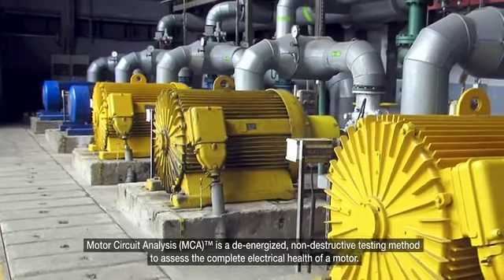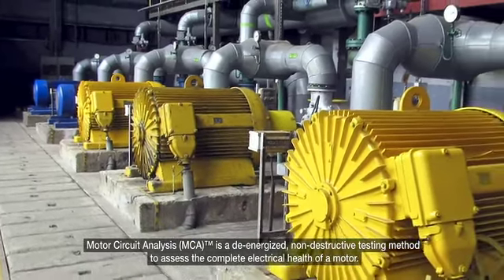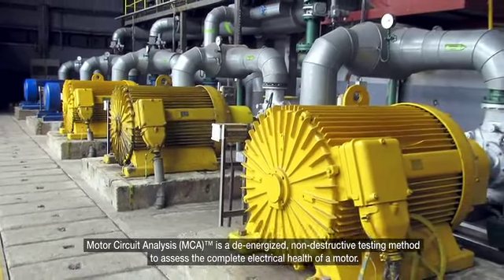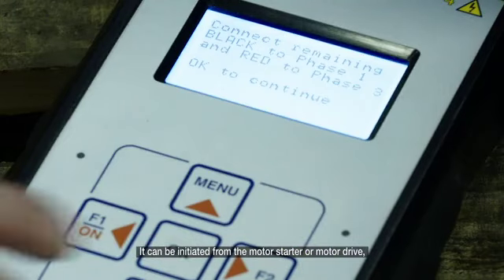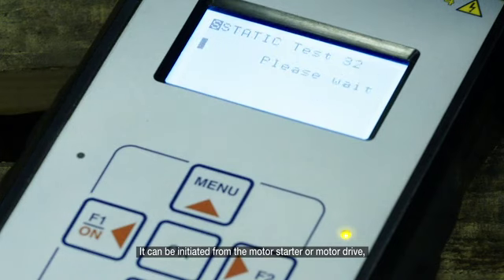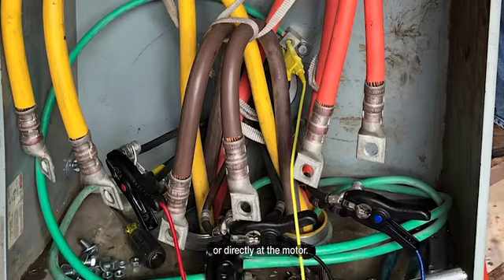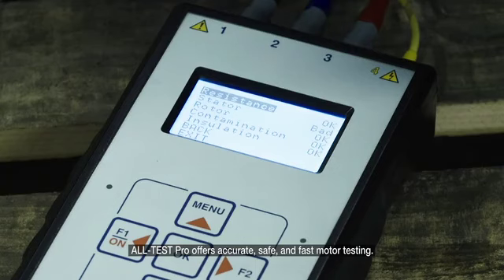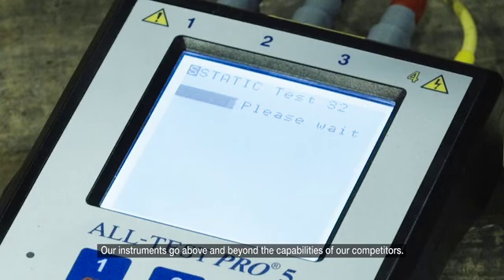Motor circuit analysis is a de-energized, non-destructive testing method to assess the complete electrical health of a motor. It can be initiated from the motor starter or motor drive, or directly at the motor. AllTest Pro offers accurate, safe, and fast motor testing. Our instruments go above and beyond the capabilities of our competitors.